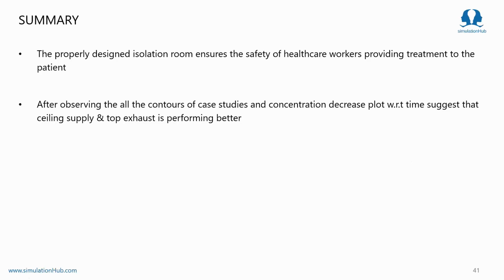As we have seen, if we use our CFD effectively, we can design an effective ventilation system that definitely provides a high level of safety to the health workers who are risking their lives daily to save us. And coming back to our standard isolation results, we conclude that our top ceiling supply and top exhaust model is a very good design and is performing better.